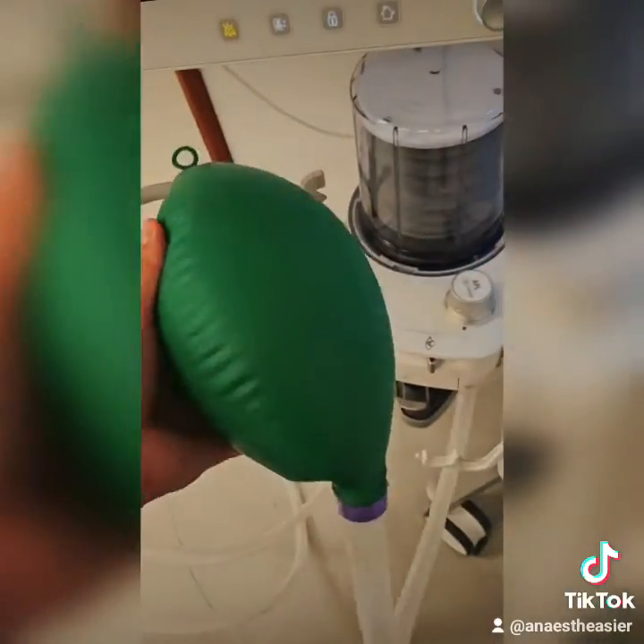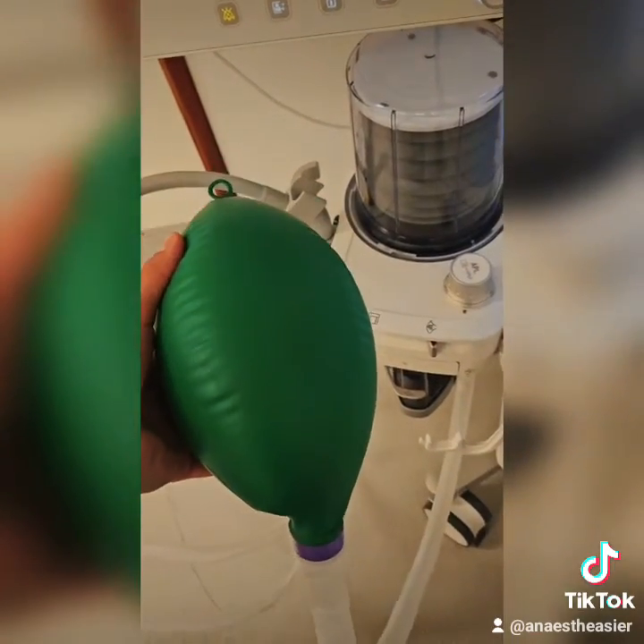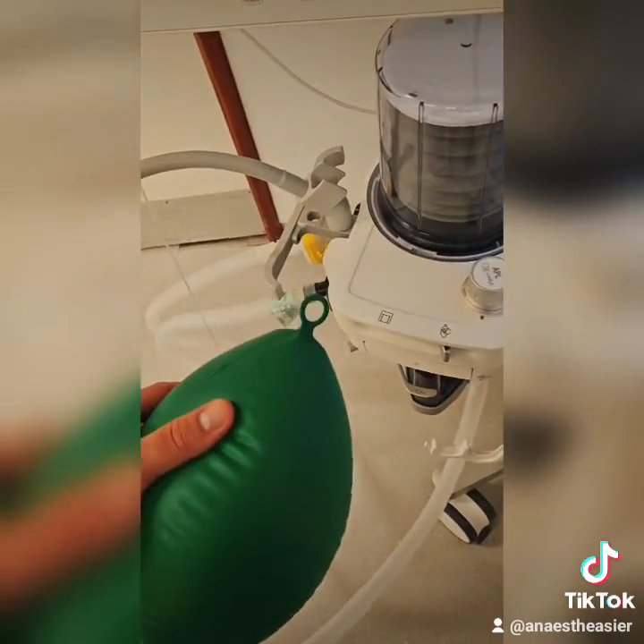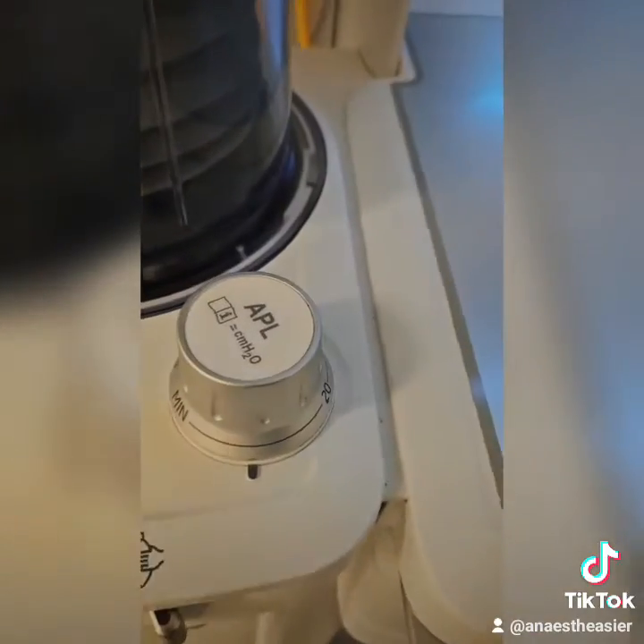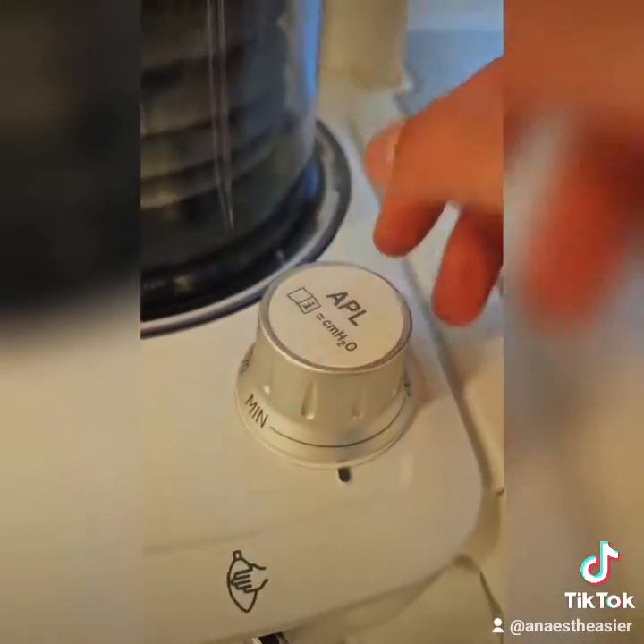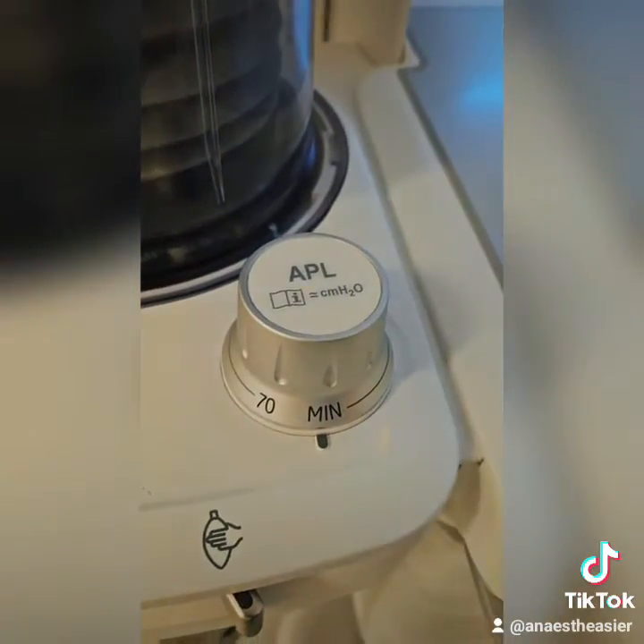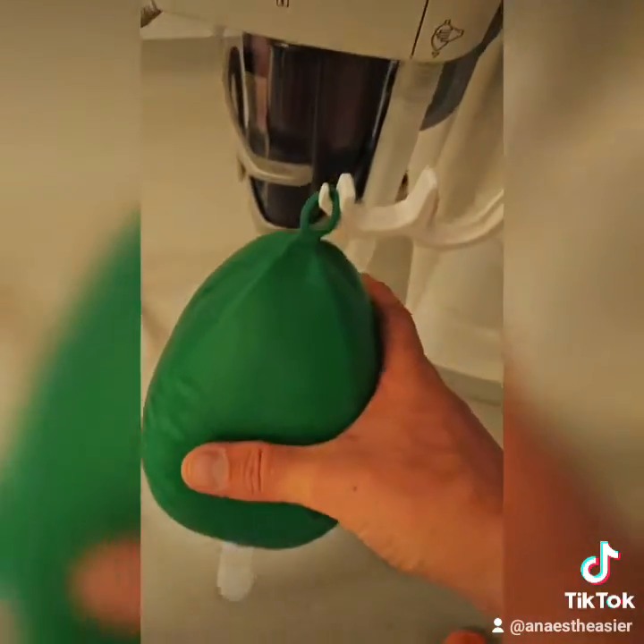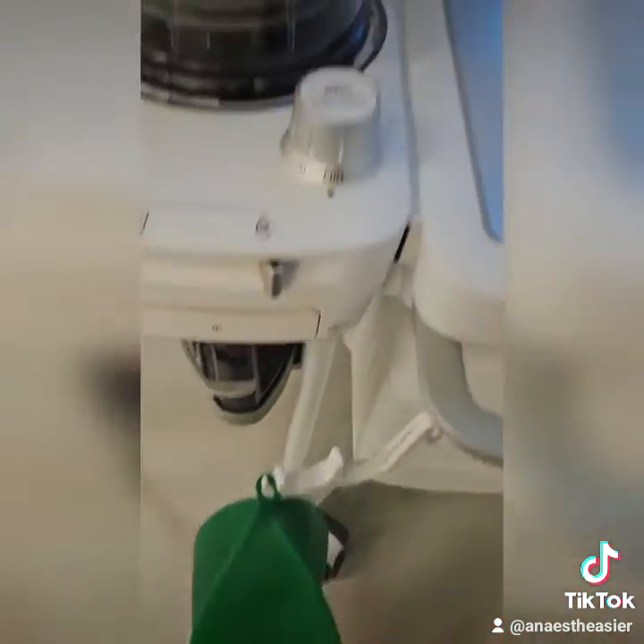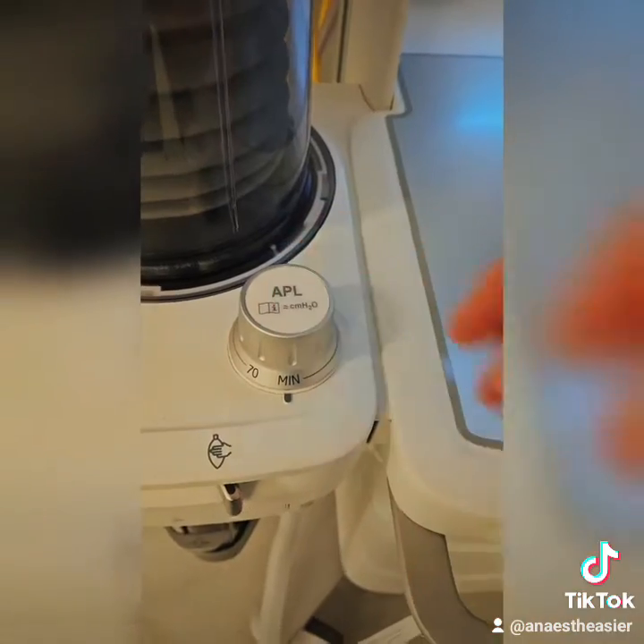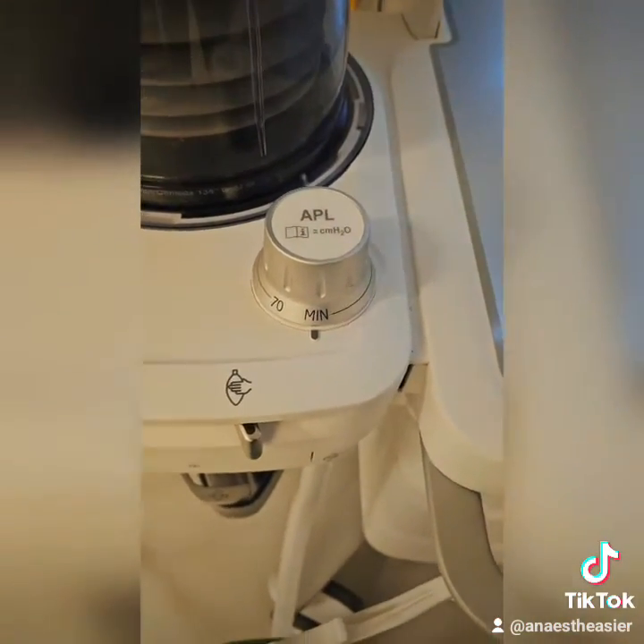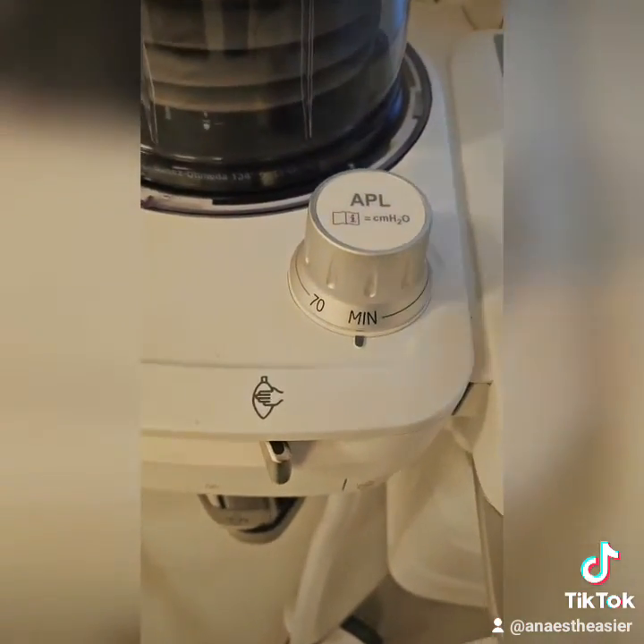The final thing it does is it acts as a reservoir of fresh gas, so they don't breathe back in any of the gas they've exhaled. This little widget here is the APL, or adjustable pressure limiting valve. So that's on minimum, which means if I squeeze the bag, then it's just all going to vent out through the safety release valve. So it means that there isn't too much pressure in the system.